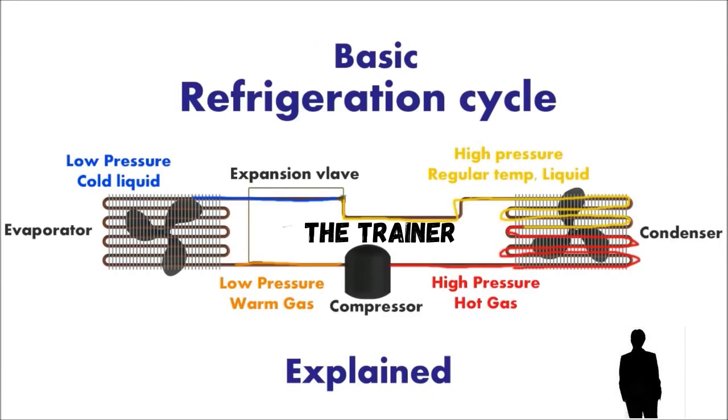As it does this, this refrigerant will begin to boil, and it will evaporate from a liquid into a gas. It does this because the boiling point of refrigerant is very low. R134A, which we looked at earlier, a typical refrigerant, has a boiling point of about -23 degrees. So you can see it doesn't take a lot of thermal energy for it to boil.